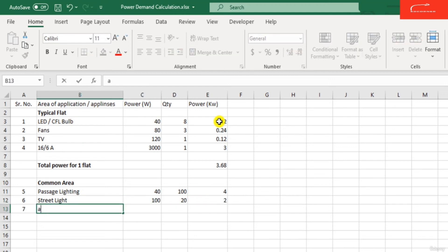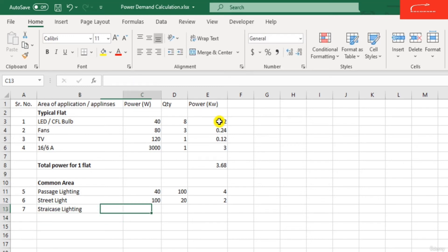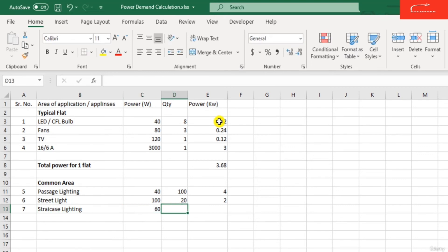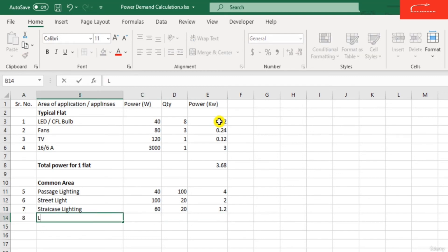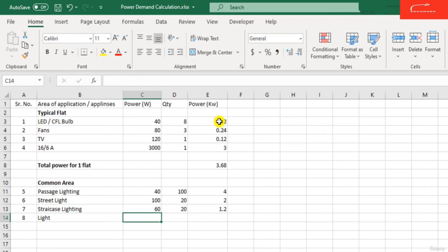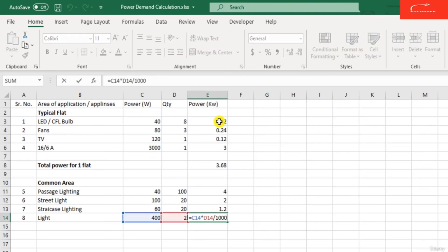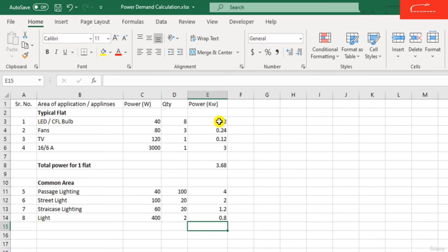For staircase lighting, each bulb is 60 watts and the number of staircase lights is around 20, so the total power required is around 1.2 kilowatt. For emergency lift services, each lift takes 400 watts, and if there are 2 lifts, the total power required for the lifts is around 0.8 kilowatt.